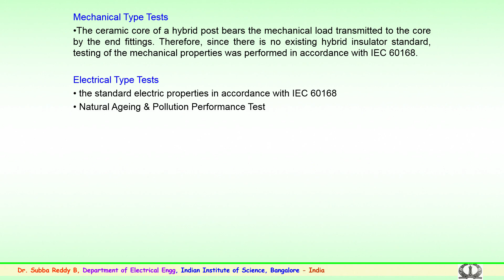Here it is understood that for AC voltage applications, hybrid post insulators are available and being manufactured, and they allow engineers to design high voltage AC air insulated substations using pollution resistant, contaminant resistant and maintenance free insulators. This type of post insulator generally combines all the advantages of traditional ceramic or porcelain insulators with those of the silicone rubber housing, without any compromise.